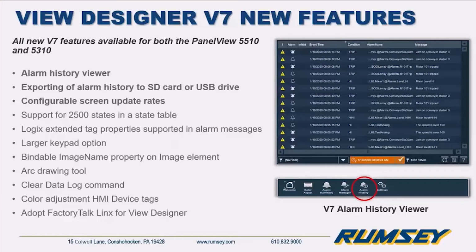And remember that this HMI doesn't use traditional HMI tags for alarming. We can directly do Logix, either instruction alarms or the new Logix tag alarms, where you totally define the alarms as we just saw in Logix, along with descriptions. Everything is done in one place. Absolutely nothing needs to be done on the HMI. So you don't need to replicate or retype descriptions and alarms. It just automatically broadcasts out to the PanelView.